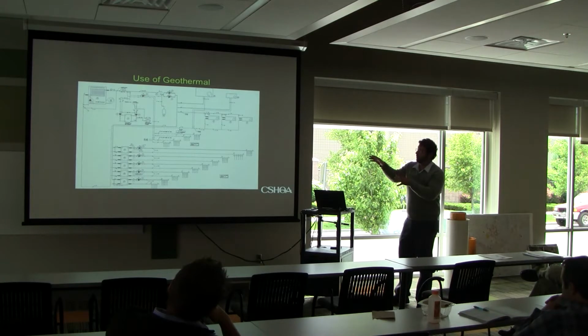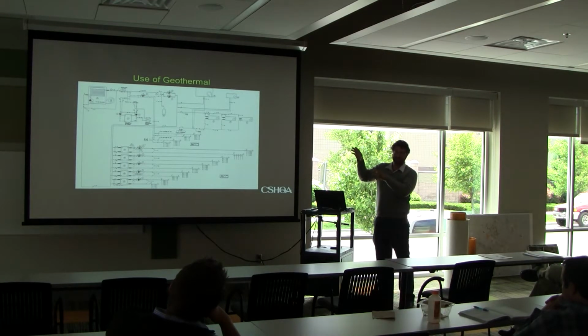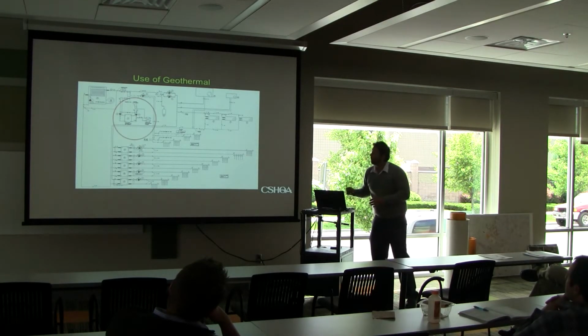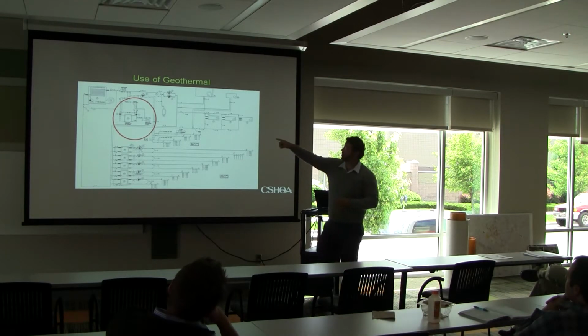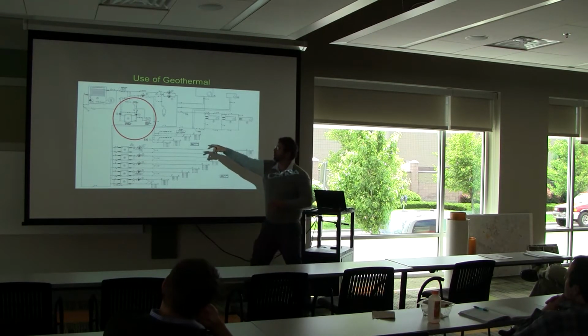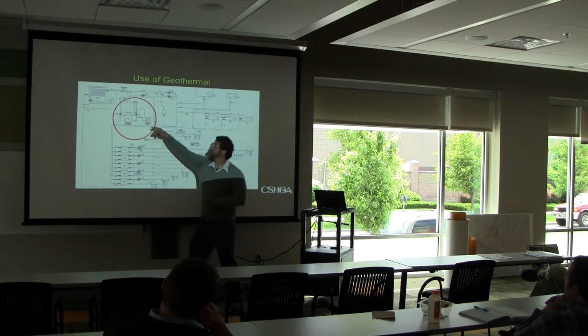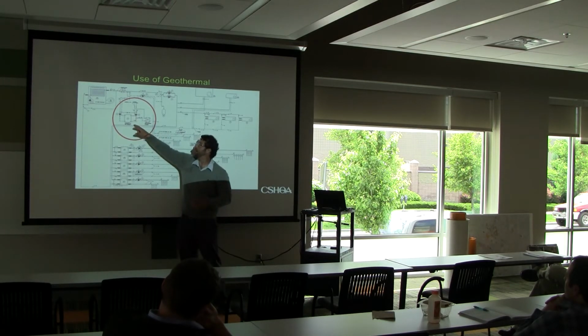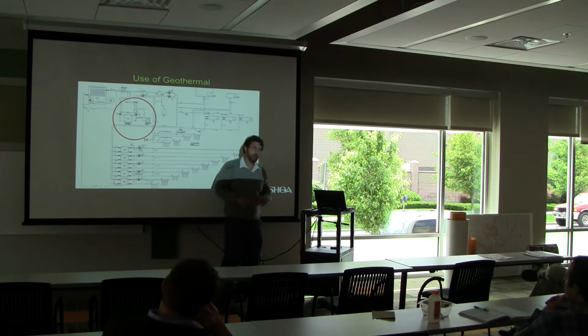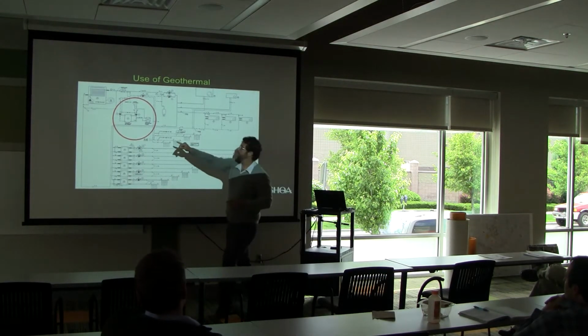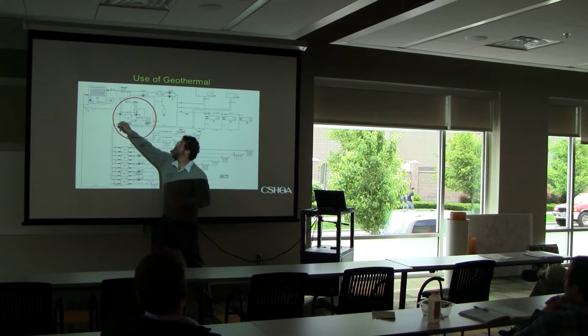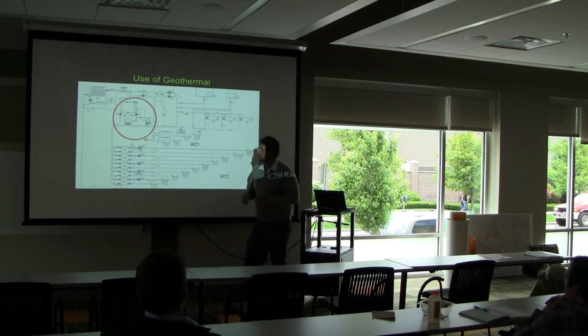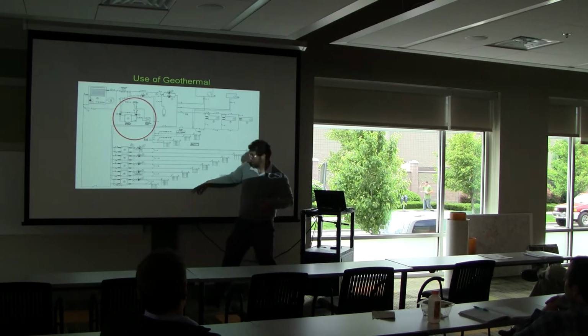This is the schematic. Very complex. This is the brainchild of Russ. I want to pay attention to this side, which is our connection to the geothermal loop. So these two pipes right here come in from the geothermal. There's one pump which circulates through a water-to-water heat exchanger. The other side of the water-to-water heat exchanger, which is this side, goes out to the building, and it's based on a control valve operation, so it tempers the source loop accordingly. Keeps it at 70 degrees, even though we start losing it as certain zones go into heating.